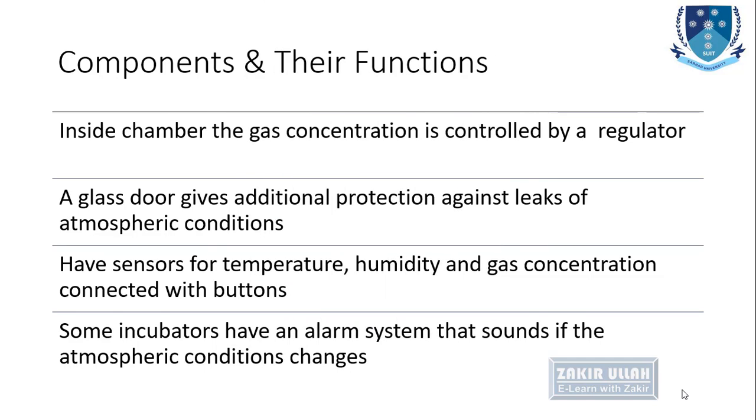Inside the incubation chamber, the gas concentration is controlled by a regulator, and this regulator is present outside on the body of the incubation chamber. Along with these, an extra glass door is also present. This door is next to the main door of the incubation chamber and it is used for protection against any leakage of the atmospheric condition inside the incubation chamber. So this door gives extra protection to the experiments or samples under process inside the incubation chamber.